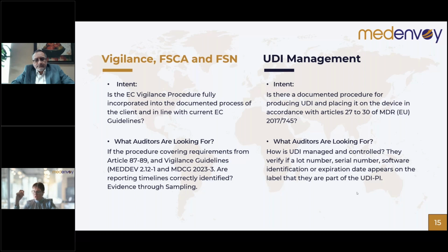Yeah, so maybe good to address here that although Switzerland again follows MDR quite nicely, in case of field safety corrective actions, they have a specific own template to be used, and they also require their field safety notices in the 3 mandatory languages for Switzerland, which are German, Italian, and French. So please ensure that if you are in such a situation, just go quickly to the Swissmedic website, where on the side on the economic operator, Swissmedic nicely laid out all the links to the forms that you can use in that case.